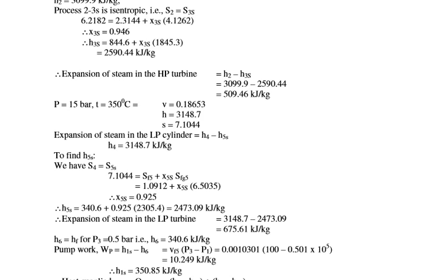The expansion work in the high pressure turbine is H2 minus H3S = 3099.9 minus 2590.44 = 509.46 kJ per kg. Then at 15 bar and 350 degree Celsius, this is again in the superheated zone. From the superheated steam table, specific volume = 0.18653, enthalpy H4 = 3148.7 kJ per kg, and entropy S4 = 7.1044 kJ per kg·K.